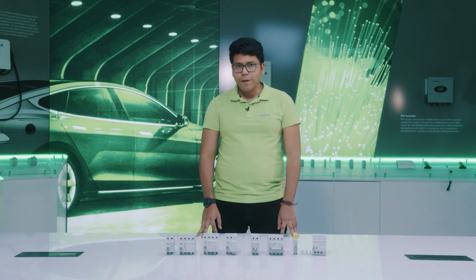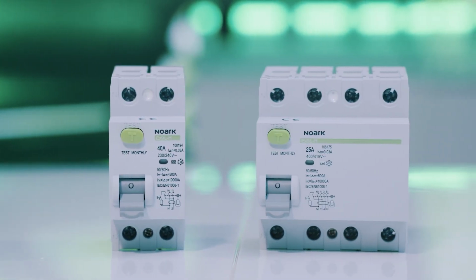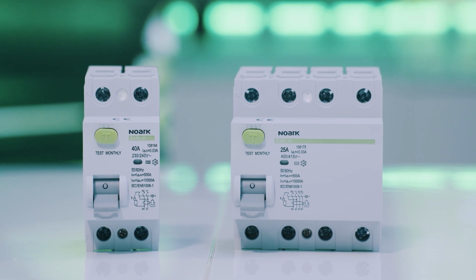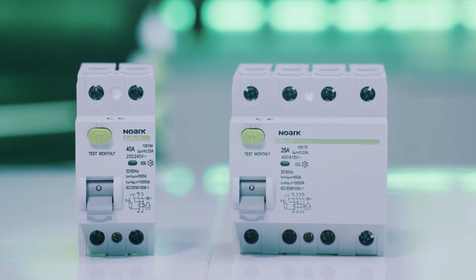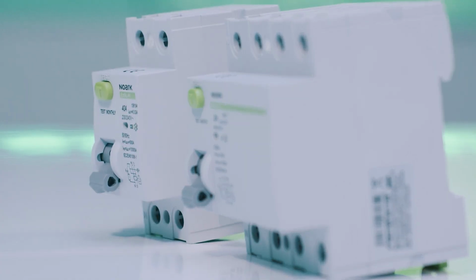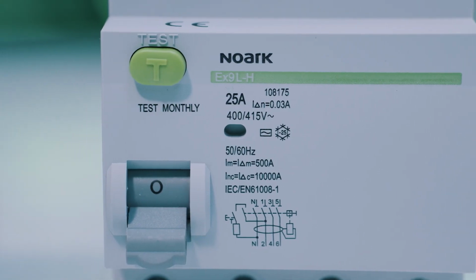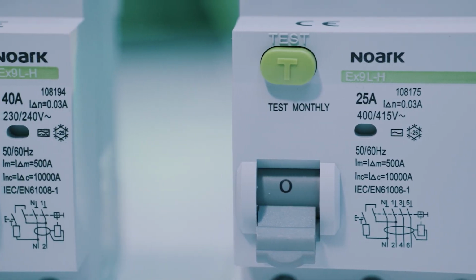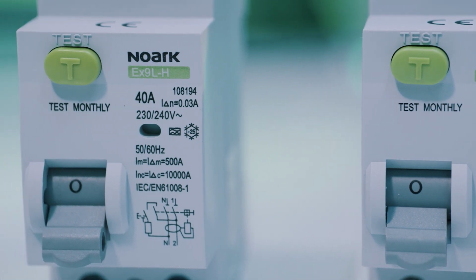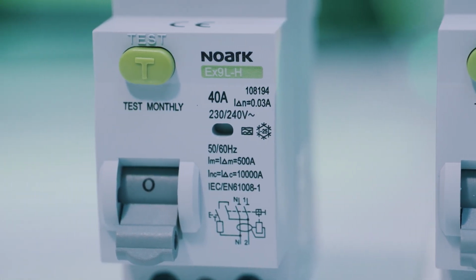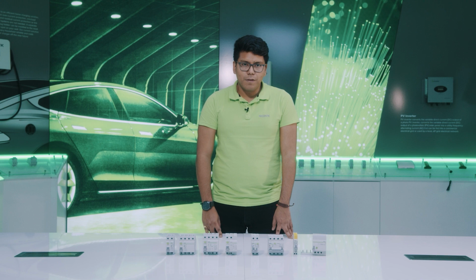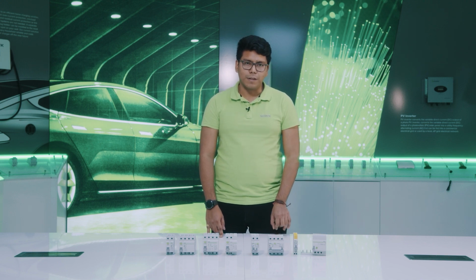First, we have our standard RCCBs EX9L. We provide them in 6 kA or 10 kA conditional short circuit strength up to nominal currents of 63 amps with AC or A type. We offer 2 pole or 4 pole versions with or without delays of G or S types. The residual current sensitivity range is from 10 mA up to 500 mA.